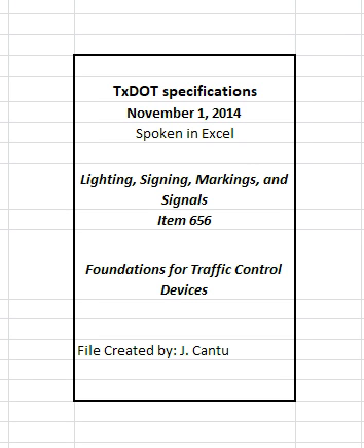Carefully align foundation, posts, and anchor bolts. Do not spring or rake posts or anchor bolts. Remove the top template after concrete has achieved initial set. Keep forms and other bracing intact until the concrete has cured at least one curing day.